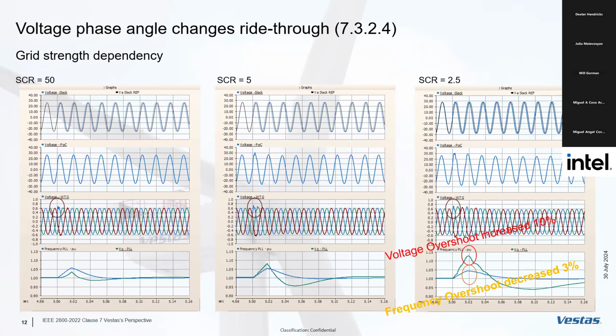You only monitor the outputs of the PLL when you are performing DQ control, and the outputs of the PLL are basically the voltage and the frequency. So the protections that will actually cause the turbine to trip when there is a phase jump are the voltage protection and the frequency protection, and they are just a consequence of the phase jump. So that's also very important to keep in mind.